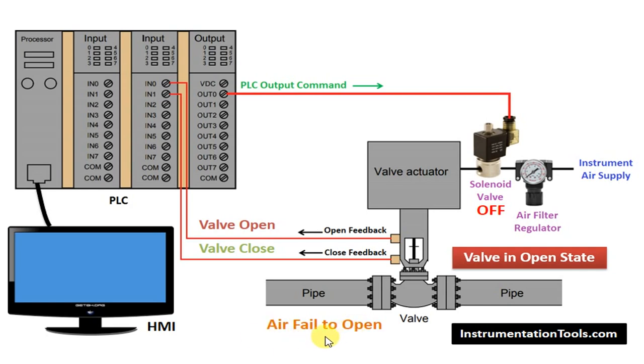That means, when there is no power supply to the valve, or when there is no air supply to the valve, the position of the valve is in open state. The default position is open state. When air is available to the valve, or the SOV is energized, then the position will change from open state to closed state.